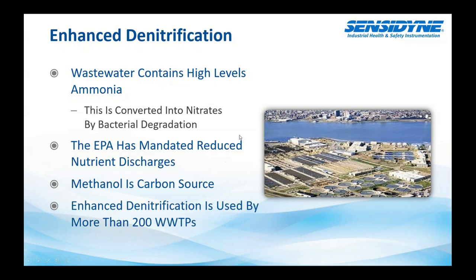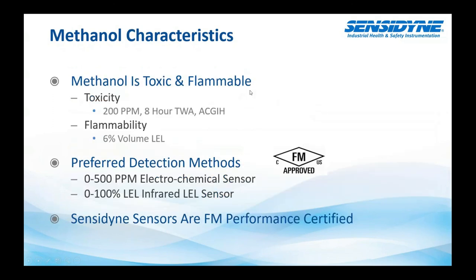Denitrification. Don't see a whole lot of applications here, but you would want to monitor, obviously, for ammonia levels, different things like that. And then a bit on methanol. Methanol has a toxicity level of 200 ppm in an 8-hour workday, so time-weighted average, this is an OSHA standard. It also has a flammability of 6% LEL, 6% volume. And LEL stands for lower explosive limit, for anybody that was wondering what LEL meant. I should have said that earlier, but LEL is just your lower limit of when that can become a hazard of exploding. Preferred detection method is going to be 0 to 500 ppm with an electrochemical sensor, and your LEL is going to be an infrared IR sensor.